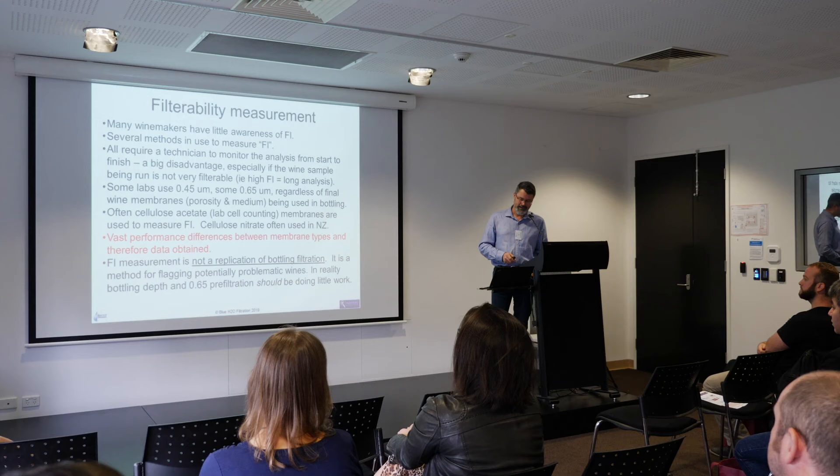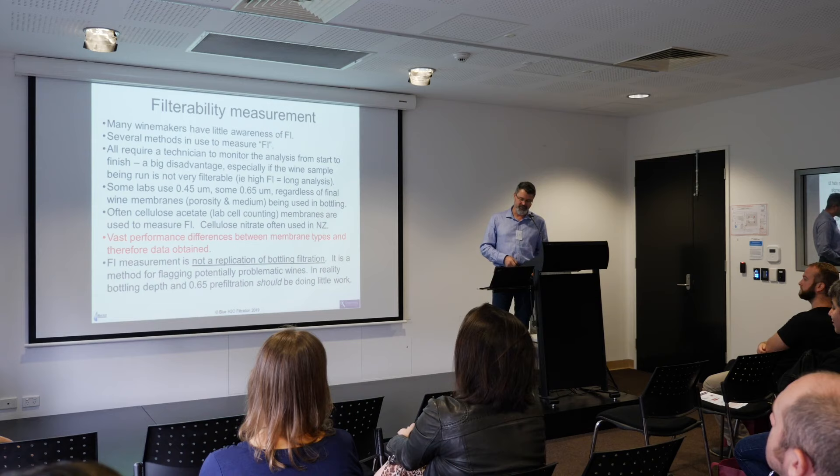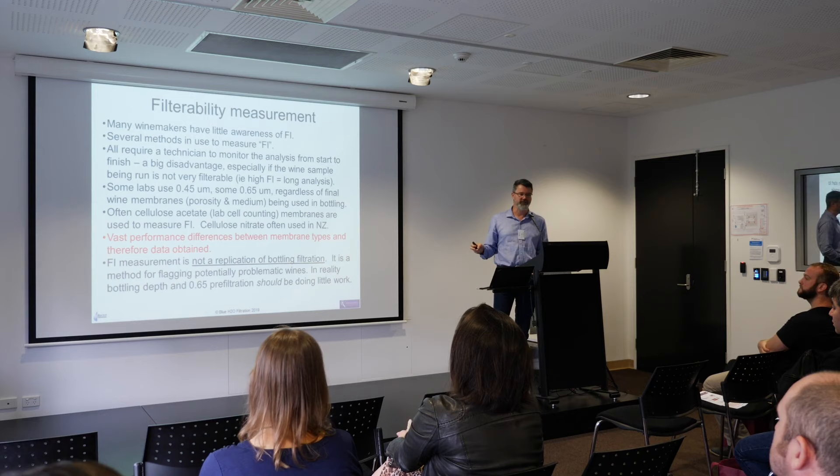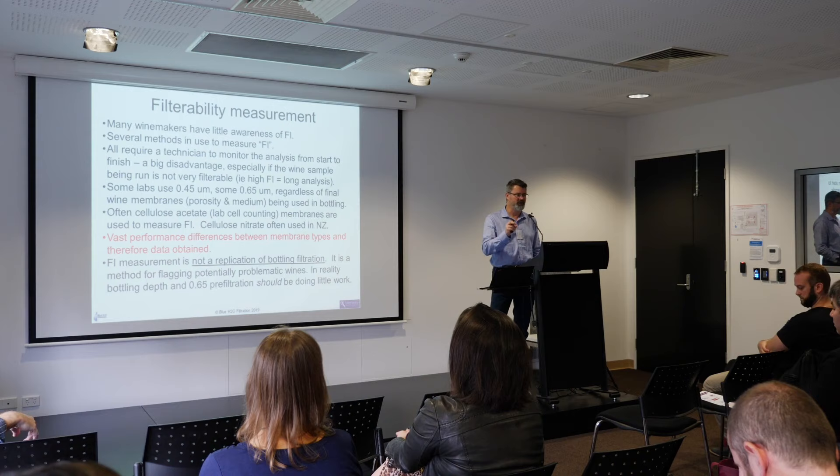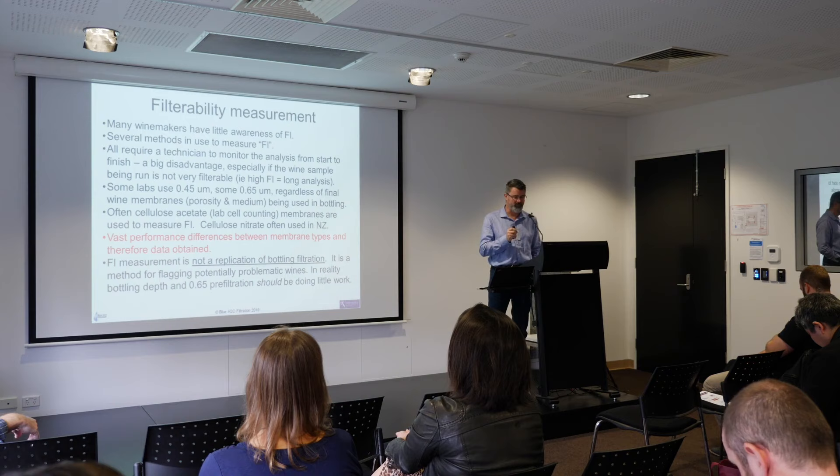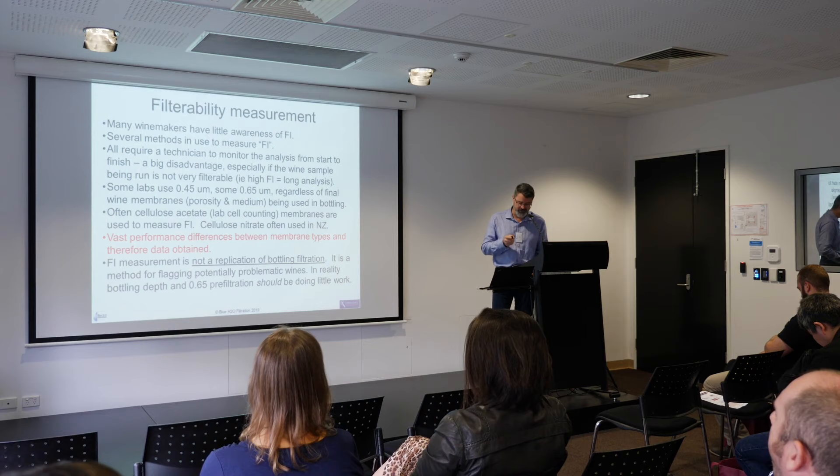There are various methods used around the world for measuring filterability. One of the main problems is that somebody has to stand there and watch it, time it, or move measuring cylinders — which is horrible. Nobody likes to do that. Automation removes the human factor. There's also variation in the test discs used — often whatever's close to hand. Filterability is a relative measurement, so the test discs should be identical to the membrane you're running on your packaging line. You often see cellulose acetate used, and in New Zealand they often use cellulose nitrate, which is a flammable goods item and really hard to ship.